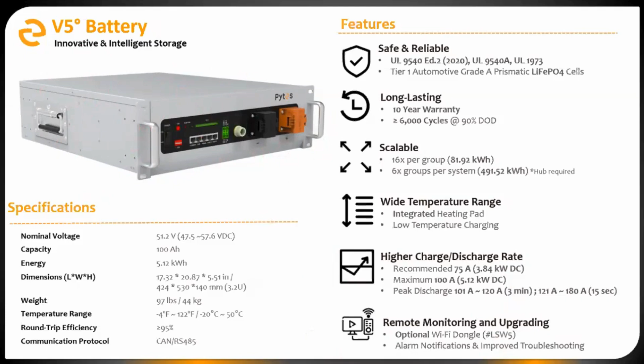It's only 0.3%. Most of those have to do with BMS issues, not cell problems or anything related to that, and many of those cases are field replaceable. Our BMS board and the power supply board in the V5 specifically can both be replaced in the field. Because the failure rate is so small, and most of those have to do with the BMS, there are very few instances where you as an installer would have to remove this battery from your installation, pack it, palletize it, and try to ship it back to us. So we try to make your lives as easy as we can, and the field serviceability on this product is, I think, a very good selling point.